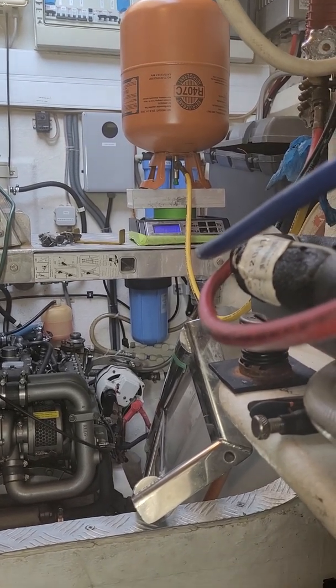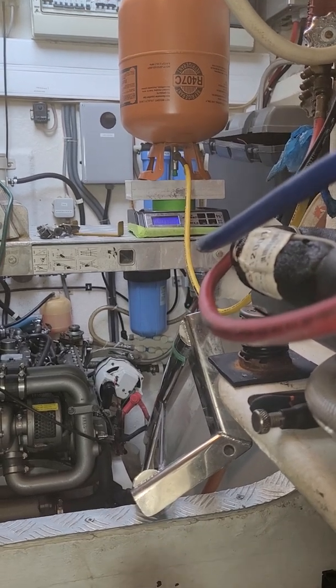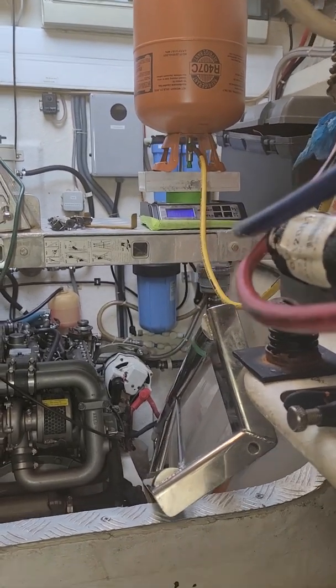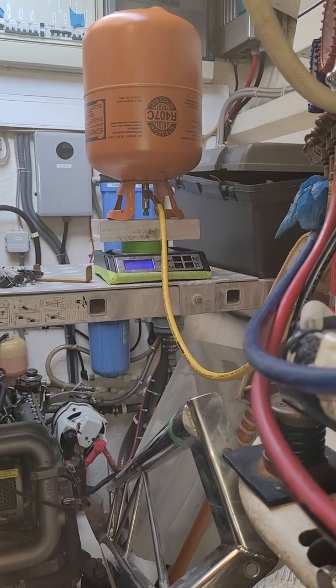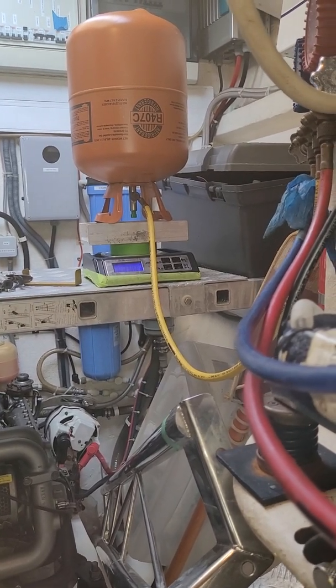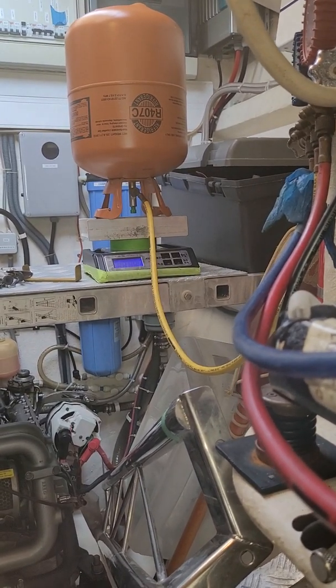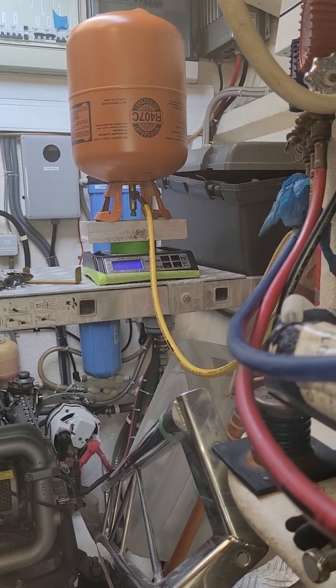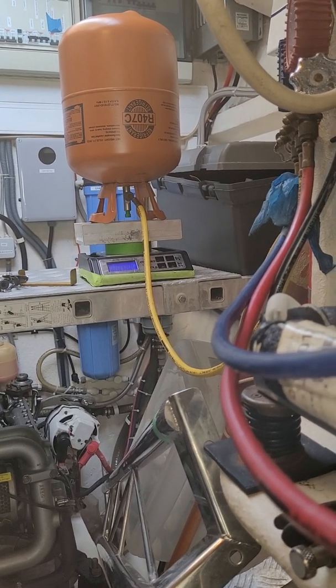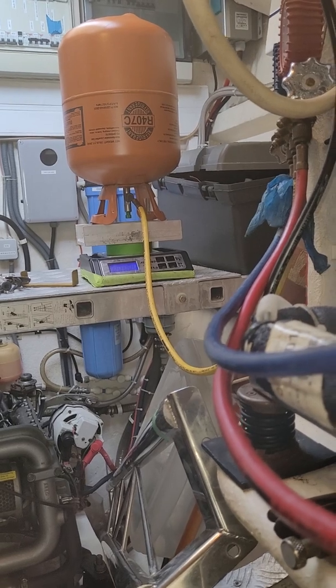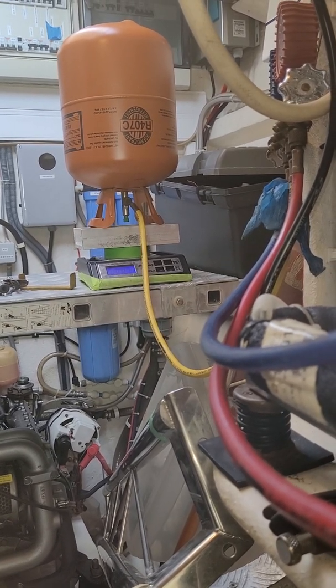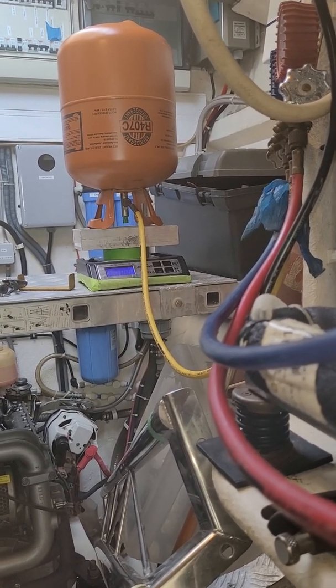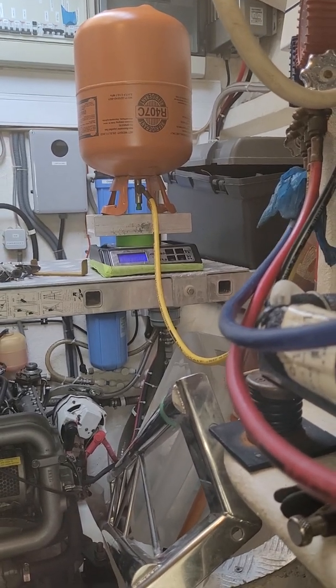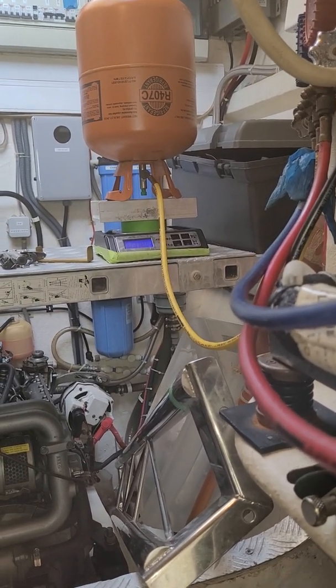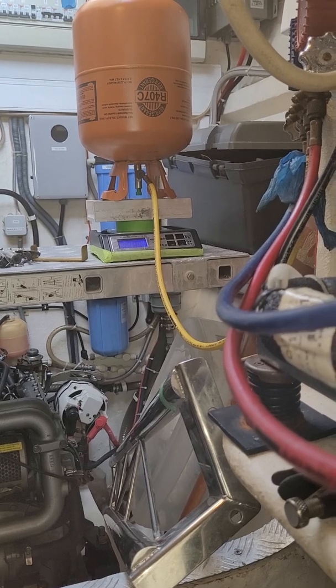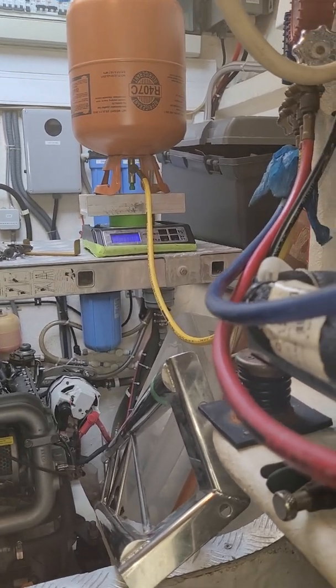So when you're filling a lot of gas, like extracting all the gas out of the system or putting all the gas back into the system, it's advisable to put the gas tank head down. So then you're filling liquid and you're going to get the proper blend. You're not going to have the one molecule boiling off faster than the other, and you might not get a good refrigerant charge in your system. So when you're charging, if you put a little bit in, it's okay to have it the right side up, but if you put a lot in, you should really have it head down. It's also much faster because you're charging liquid instead of gas.